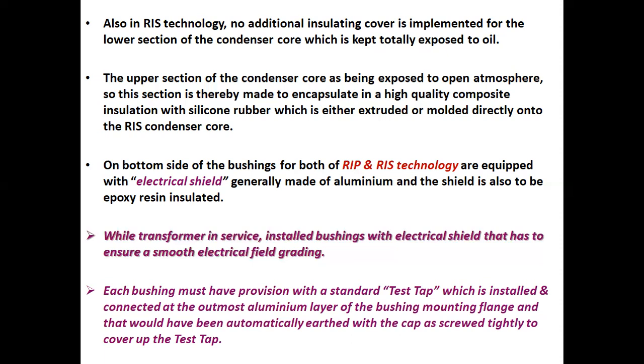While the transformer is in service, installed bushings with an electrical shield ensure smooth electrical field grading. Each bushing must have provision for a standard test tap, which is installed and connected at the outermost aluminum layer of the bushing mounting flange, and that would be automatically grounded with the cap screwed tightly to cover the test tap. That is the same as the OIP bushing test tap.